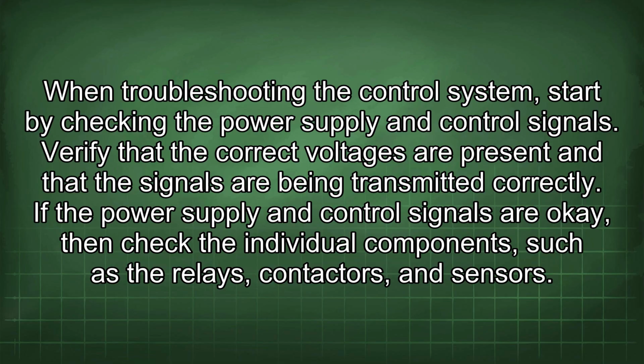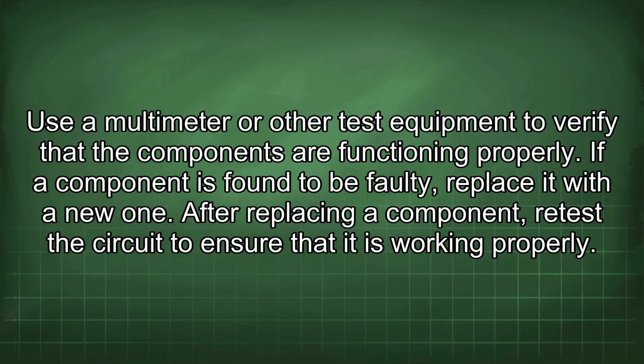Verify that the correct voltages are present and that the signals are being transmitted correctly. If the power supply and control signals are okay, then check the individual components, such as the relays, contactors, and sensors. Use a multimeter or other test equipment to verify that the components are functioning properly. If a component is found to be faulty, replace it with a new one. After replacing a component, retest the circuit to ensure that it is working properly.